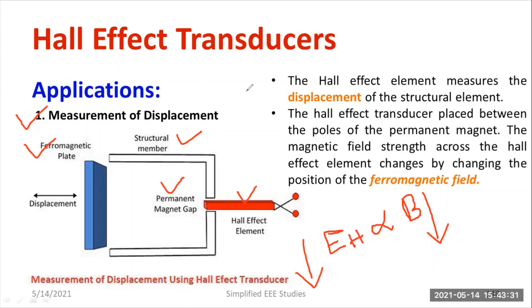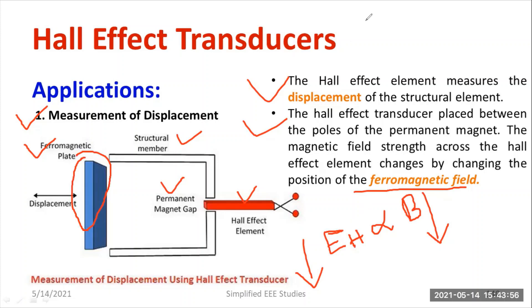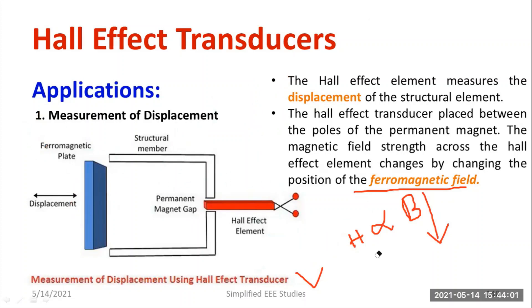The Hall effect element measures the displacement of a structural element. The Hall effect transducer is placed between the poles of a permanent magnet, creating a transverse magnetic field. The magnetic field across the Hall element changes by changing the position of the ferromagnetic plate, identifying changes in position. Accordingly, the EMF will vary, and you can measure changes in displacement in terms of Hall EMF.